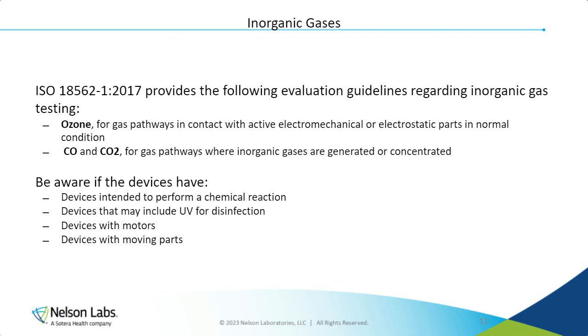Additionally, your specific device may need to be tested for inorganic gases, such as ozone, carbon monoxide, or carbon dioxide. Some guidance is provided if your device has electromechanical or electrostatic parts, or just if inorganic gases could obviously be generated. For a device to generate ozone or other inorganic gases, although it is uncommon, it's not unheard of, and there's a few devices that come to mind.